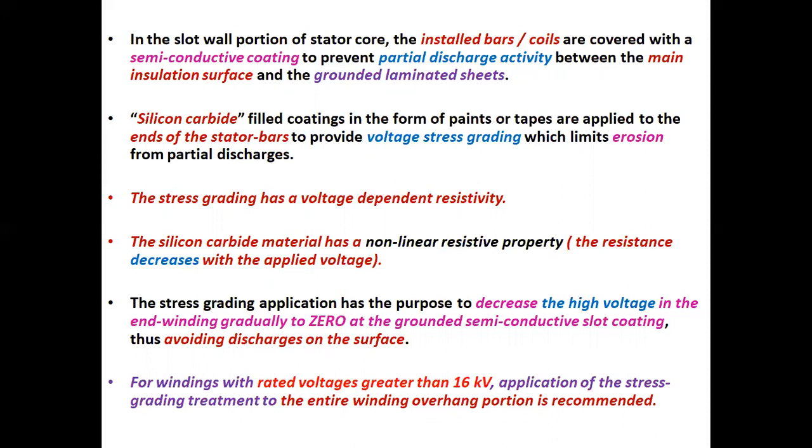Silicon carbide filled coatings in the form of paints or tapes are applied to the ends of the stator bars to provide voltage stress grading, which limits erosion from partial discharges. The stress grading has a voltage dependent resistivity. The silicon carbide material has a non-linear resistive property.